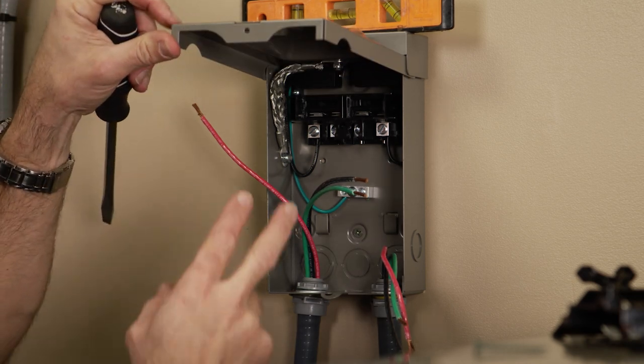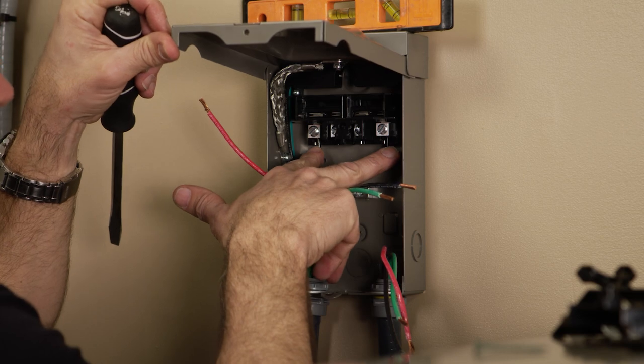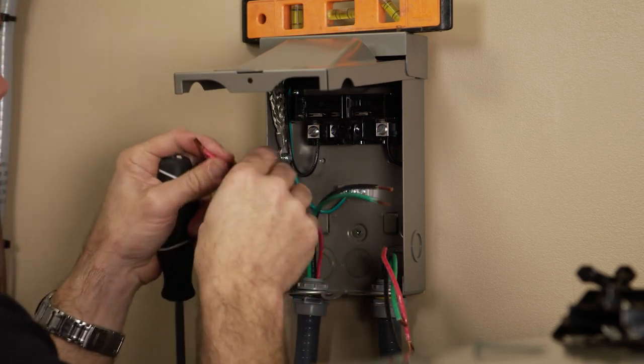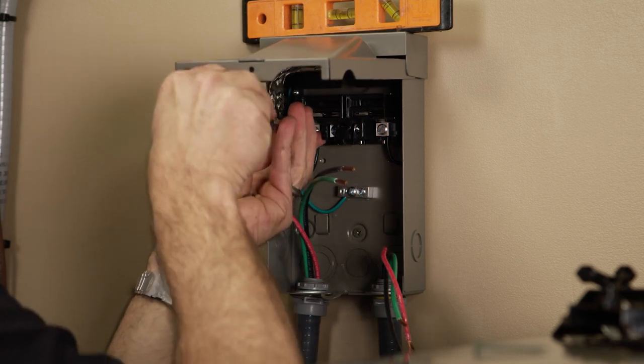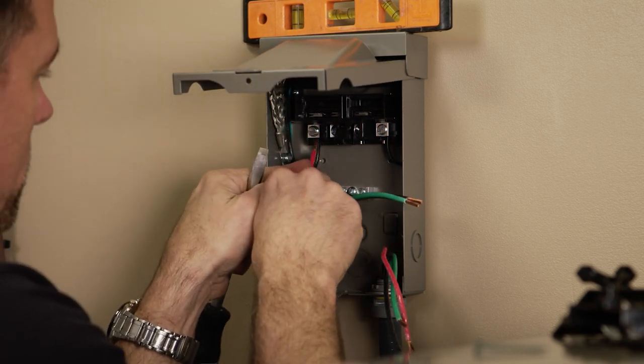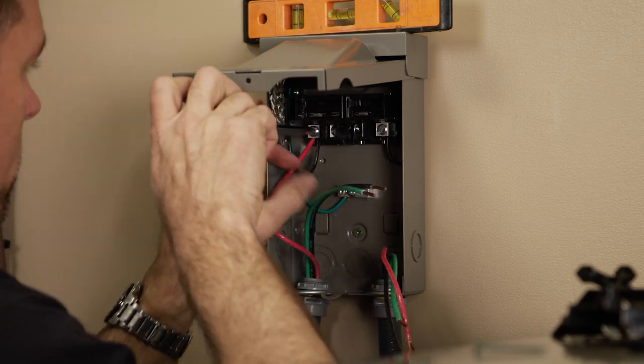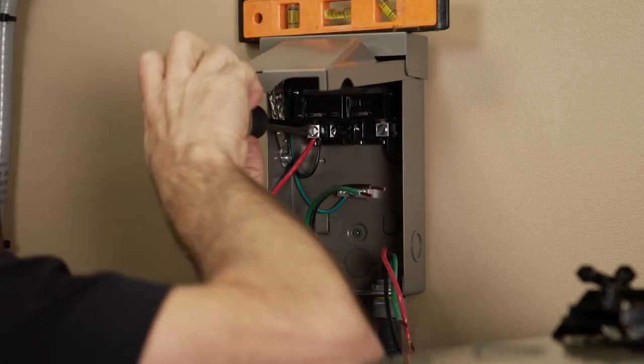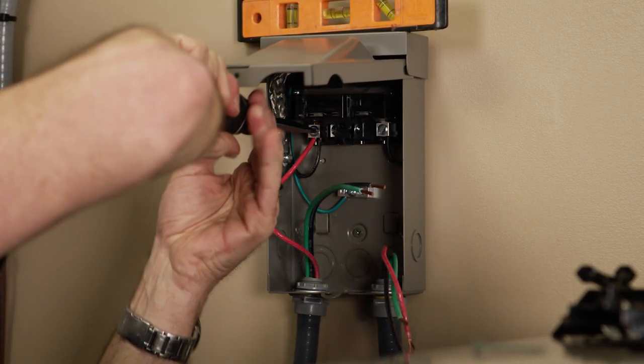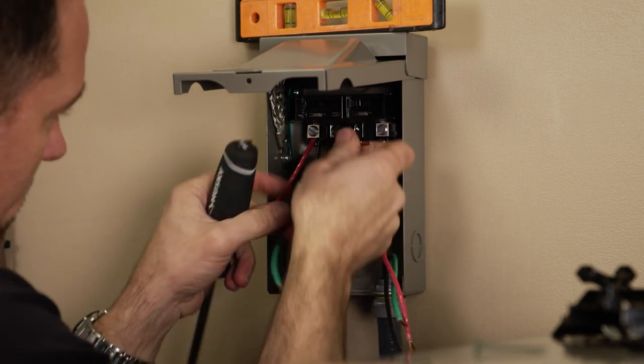So from the factory the surge protector is pre-wired to the line lugs on the disconnect here. So we're just going to loosen the screws. Just one wire at a time, make sure the wire didn't fall out. Make sure that's tight. Move on to the other side.